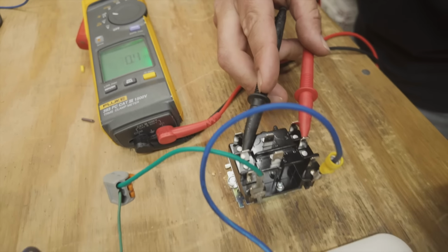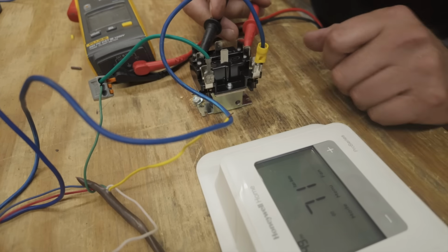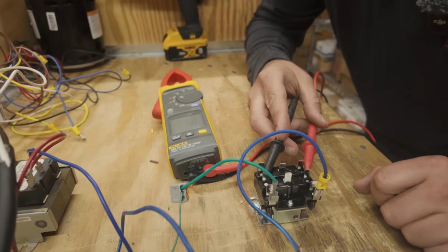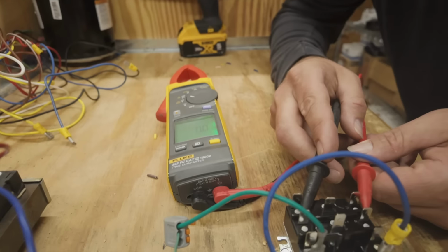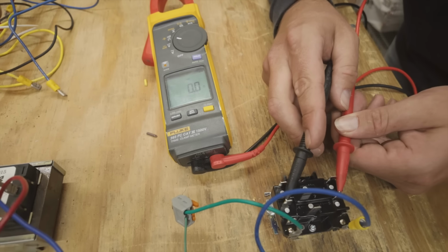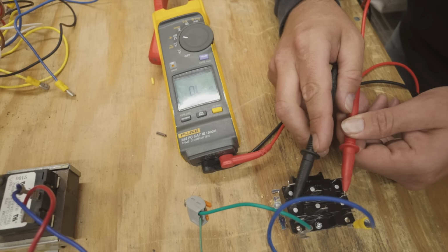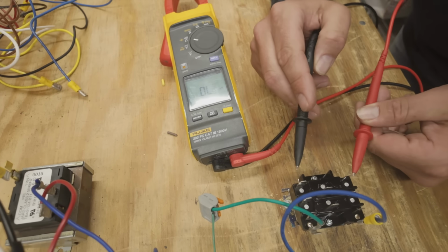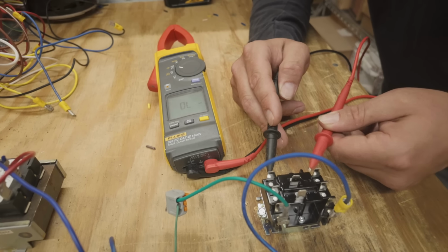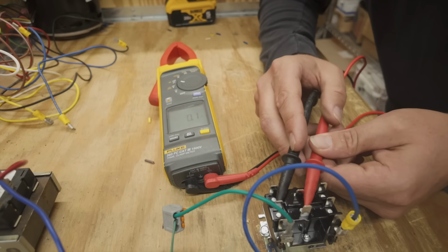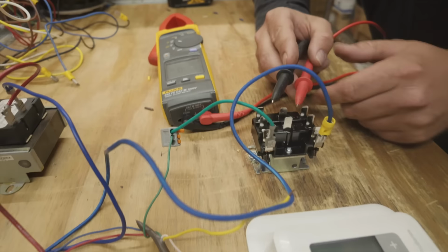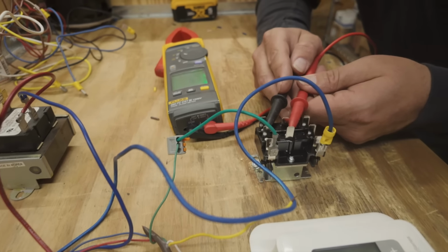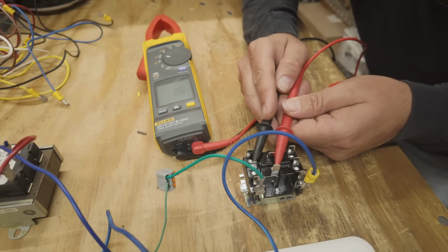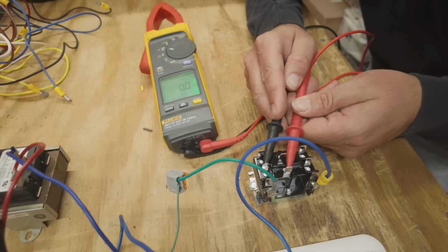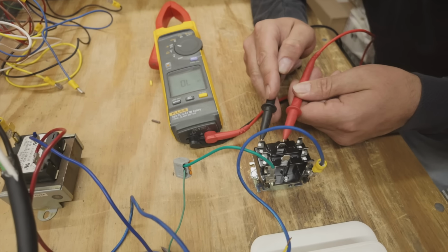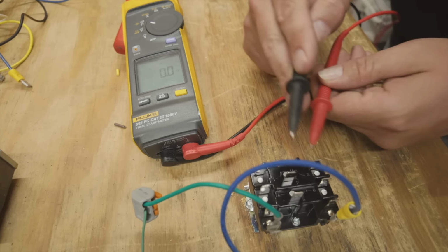Now watch this. I'm going to leave it there on 4 to 5. I'm going to turn my fan off on the thermostat. Watch what happens. Here we go. 4 to 6. Oh, 4 to 6. I hope I didn't say 4 to 5. So 4 to 6, look. Look at that. It opened up, because it's normally open. Stays normally open. These are normally closed now. But if I push fan on again, and it clicks, these normally closed contacts are going to open. See? Opened. Open. But now these are closed.